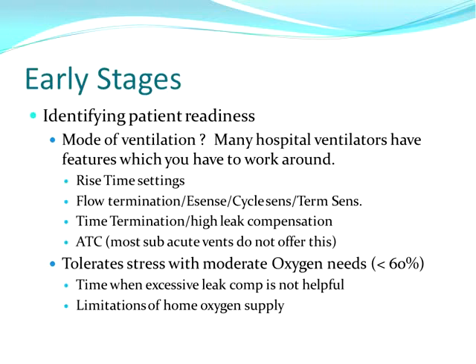The second thing might be flow termination, E-sense, cycle sense, termination sensitivity. Unfortunately, lots of ventilators call this something different. So it's pretty much the same thing on every ventilator. It's the percentage of peak flow at which a pressure support breath will end, but it may be labeled differently. Again, different ventilators may have different variances. Some of them may go all the way down to 10% and up to 80%. Some of them may go from 10% to 40%.